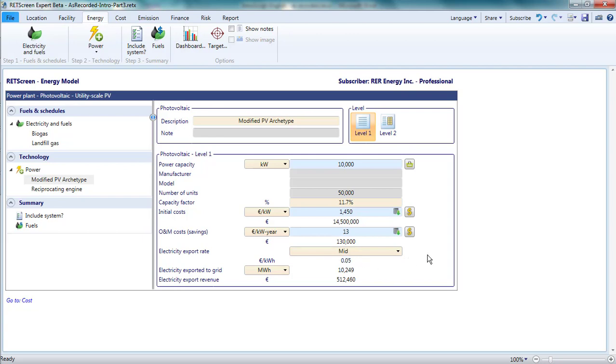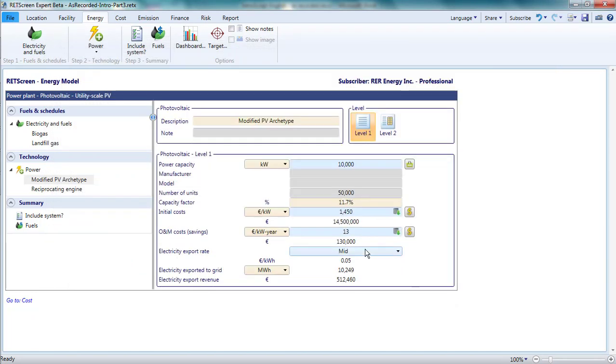Third, while most of the input parameters in the energy page are for specifying the physical characteristics of the project, it does include inputs for the initial costs and annual operating and maintenance costs. Clicking on the dollar sign icon beside these inputs opens a cost database which suggests costs on a per kilowatt basis. I'm not obliged to adopt these suggestions. At the time I'm recording this, for example, initial costs for utility-scale PV systems in Germany are around 750 euros per kilowatt, so I will enter that. For the O&M costs, I will enter 8 euros per kilowatt per year.